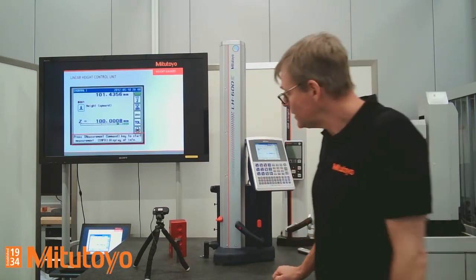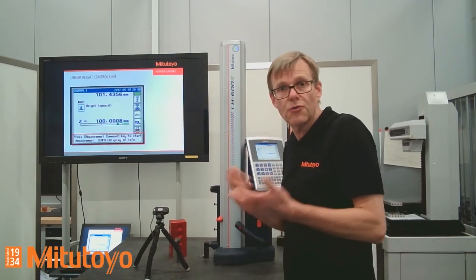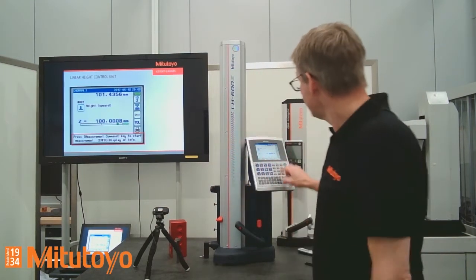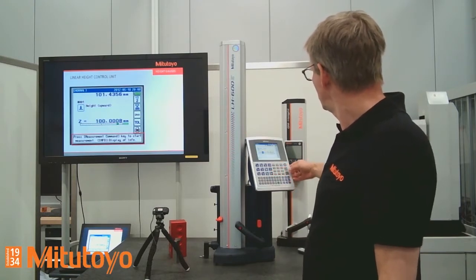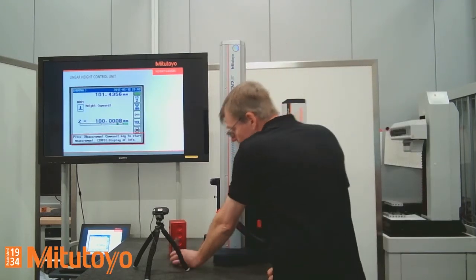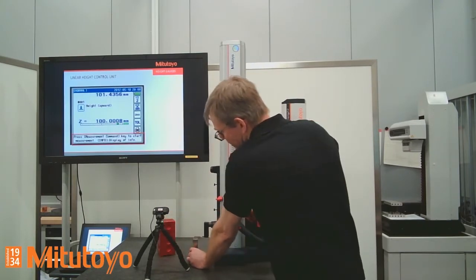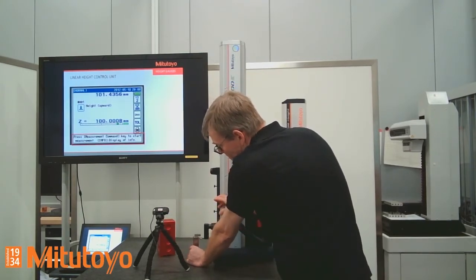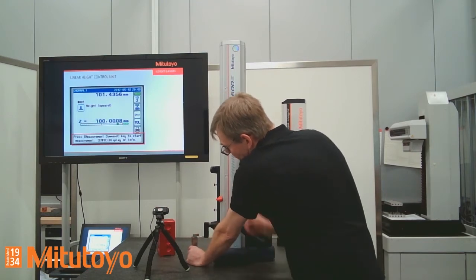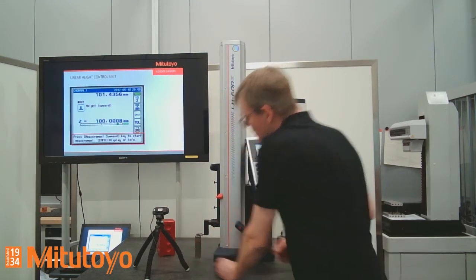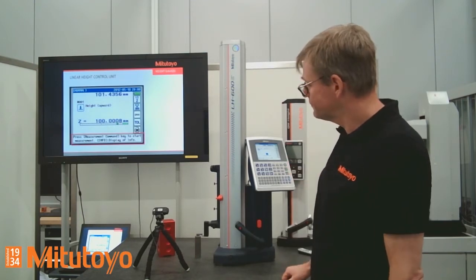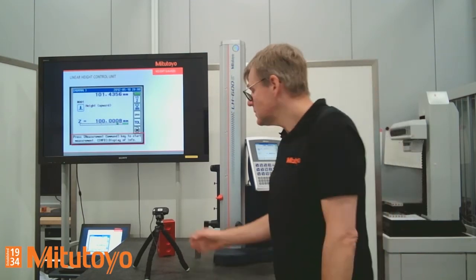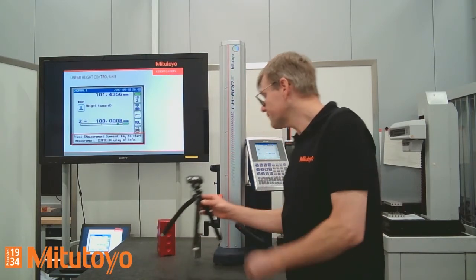So next step will be, okay, this is my first start. So in the early beginning, I put a new probe inside. So the first thing I have to do is to make a probe calibration. Okay, let's do it. So I will put this one. And then I use the setting block for this. So you can see the machine is moving up this surface and then on the next one. That's it. So we can have a look at the controller.